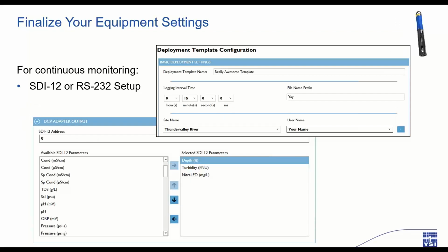Also, for long-term monitoring, setting up your deployment settings is critical, especially if you're connecting your sonde to a data logger. In your deployment settings, you'll need to set an appropriate logging interval, and this is how frequently you want the sonde to record data, as well as make any adjustments needed to the SDI-12 or RS-232 output so that the data you're collecting aligns with that of the data logger you're connecting to.